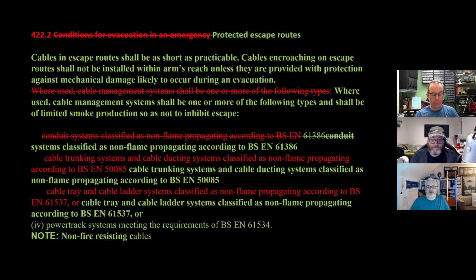General rule of thumb I grew up with was London Underground - you could use a plastic wall plug on something small and lightweight. If it fell off, it wouldn't cause injury and harm. Everything else, I would use metal. They are allowed on the Underground, but only for little small poster frames and stuff like that. Anything like containment or electrical systems or cabling, it's fire rated Chemfix, studs, Unistrut, the whole lot. Only for small things - poster holders, poster frames, leaflet holders - things that aren't going to prematurely collapse and entangle a firefighter. It'll just fall on the floor and they can step over it.